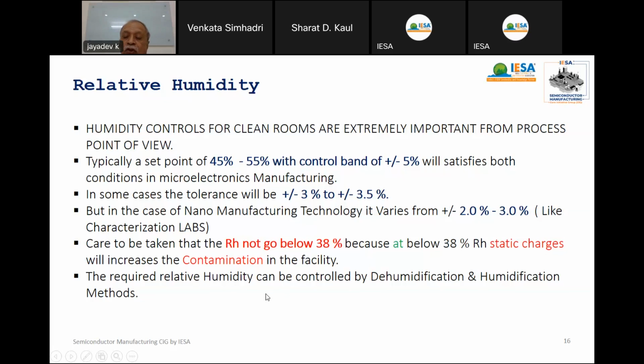Sometimes we may have to use dehumidification or humidification units. For dehumidification, when you take the outside air, you can use cooling coils up to a certain point. Apart from that, we remove the moisture from the outside air using a dehumidifier, so that we can reduce from 82% to 45% using the dehumidifier along with a heater. Suppose relative humidity goes below 40%, then we have to add some water vapor using humidification.